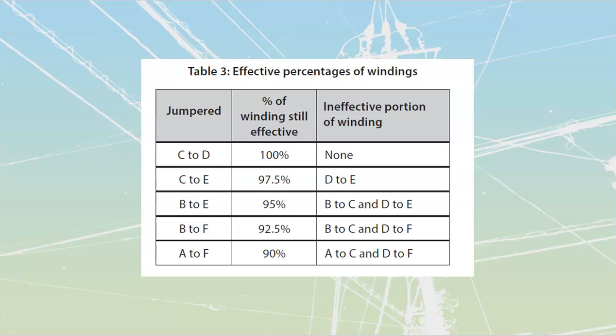If somebody put this together, in a lot of cases I'd see that instead of starting at 95% and dropping down 5% then going up to 100%, it would be more common for this to be your 100, this your 102.5, this your 105%, and this your 97.5, with this being your 95% tap.